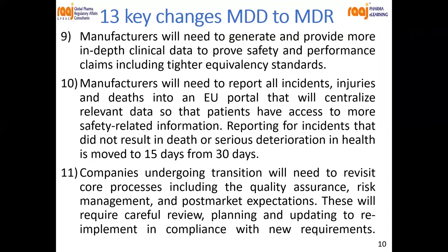Reporting for incidents that did not result in death or serious deterioration in health is moved to 15 days from 30 days. So you must have heard that in the pharma industry it is called pharmacovigilance. Here it is called materiovigilance. So whatever injury or death happens, everything is recorded and updated on the EU portal, and all the updated guidelines related to safety information you will find on the EU portal.